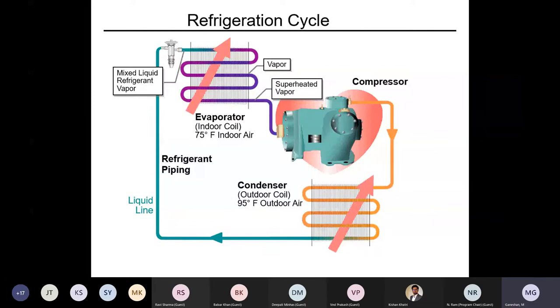In a typical refrigeration cycle, we have three major components, everybody knows: compressor, condenser, evaporator, and of course a flow control. It may be a 1 ton air conditioner or up to 10,000 tons, the fundamentals remain the same. Once you understand this, you can troubleshoot and find out the reasons for any issue.